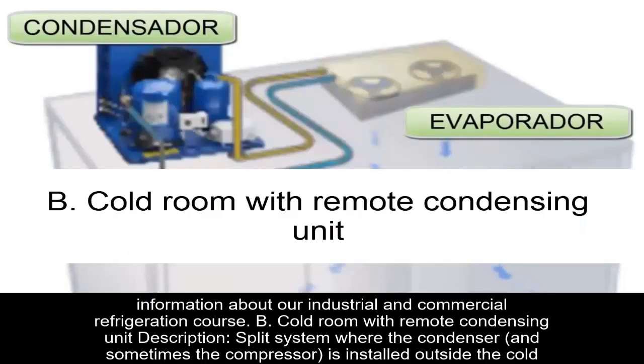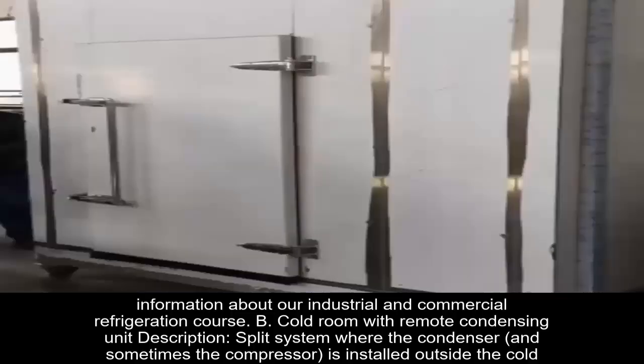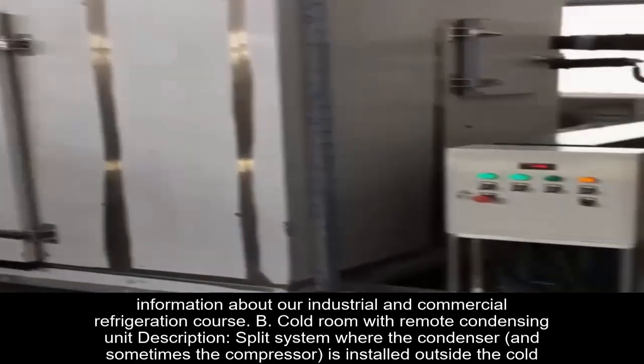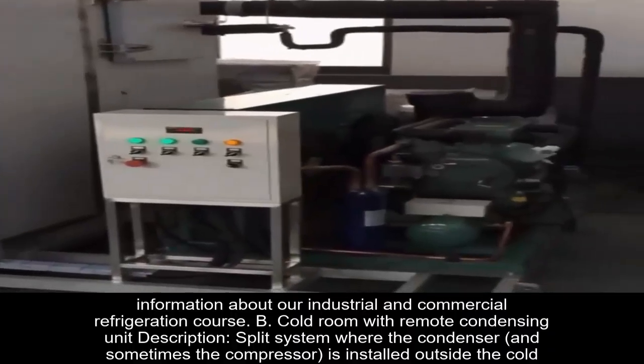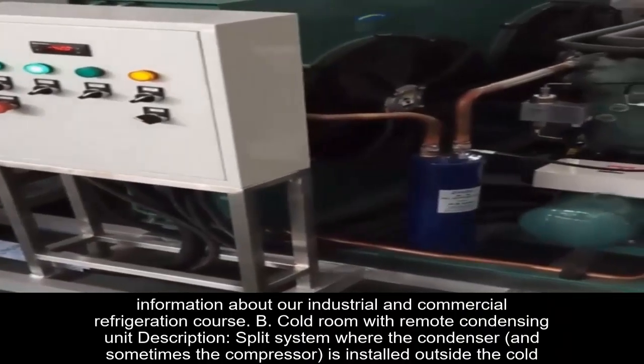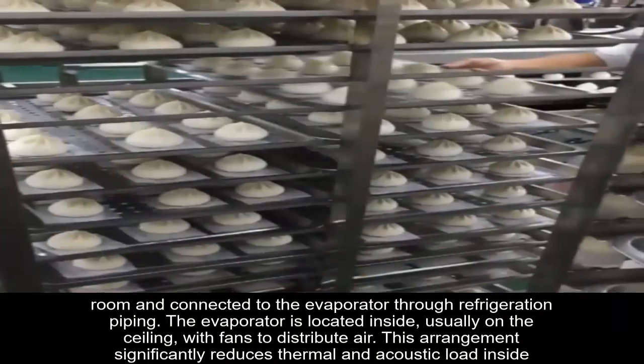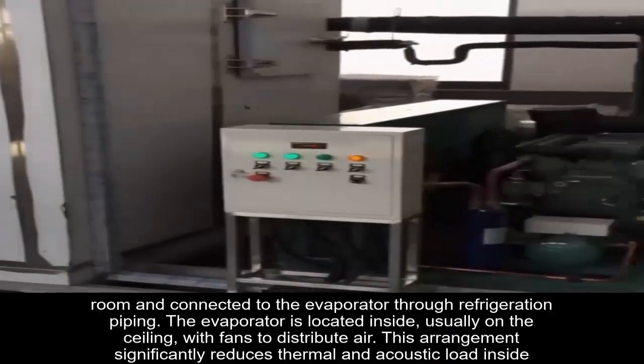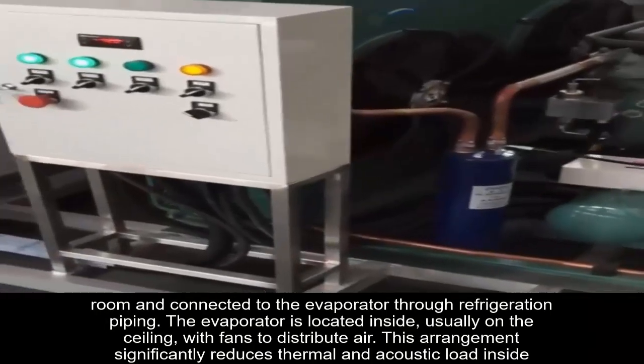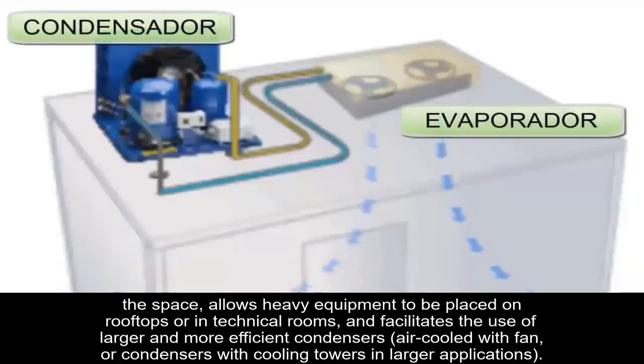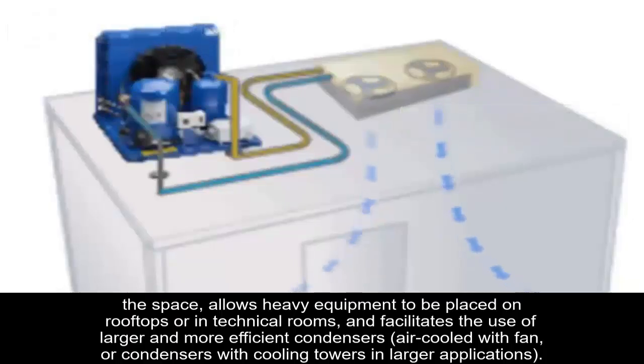B. Cold room with remote condensing unit. Description: split system where the condenser, and sometimes the compressor, is installed outside the cold room and connected to the evaporator through refrigeration piping. The evaporator is located inside, usually on the ceiling, with fans to distribute air. This arrangement significantly reduces thermal and acoustic load inside the space, allows heavy equipment to be placed on rooftops or in technical rooms, and facilitates the use of larger and more efficient condensers, air-cooled with fan, or condensers with cooling towers in larger applications.